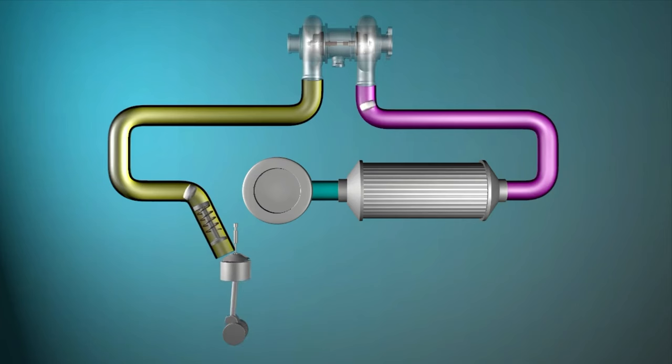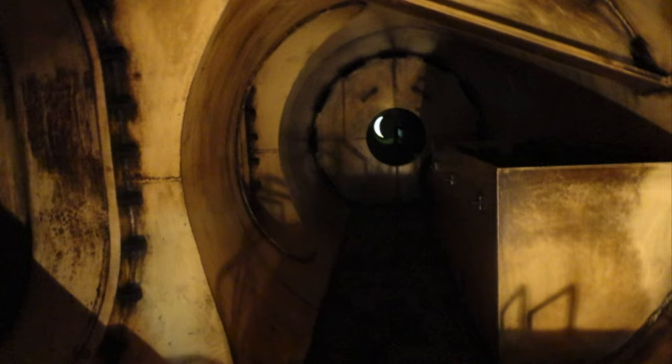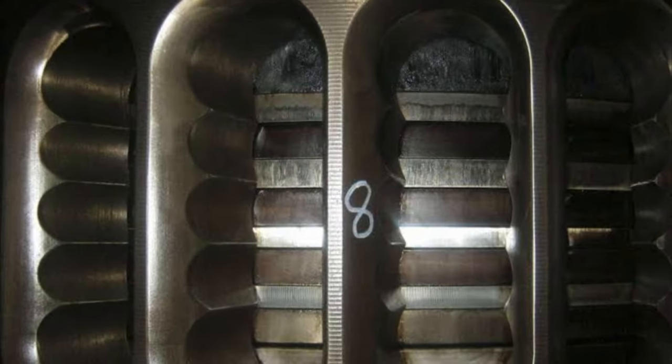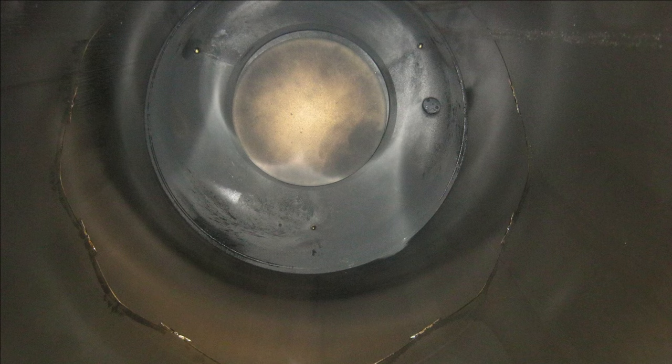This cooled air is then supplied as fresh air inside the scavenge trunk of the engine from where it takes the supply of combustion air through scavenge ports of the liner.